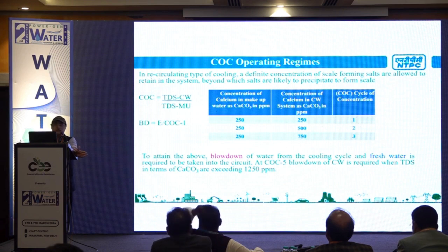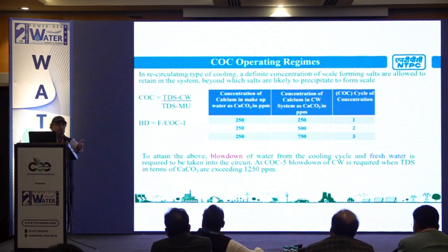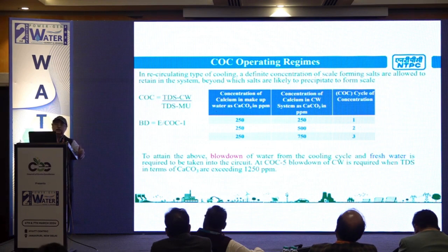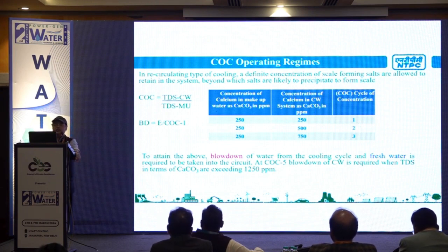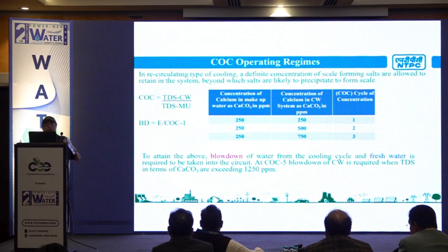COC, as you know, is the TDS of our CW system divided by the TDS of the makeup water. There are different ways to measure COC, some measure through TDS itself, some through magnesium, calcium, or chloride. At Jhajjar we determine COC in terms of magnesium, because magnesium is a stable salt, lesser influenced by external factors like calcium or silica in our atmosphere. So we are determining COC as the magnesium in our CW water divided by the magnesium in our makeup water.